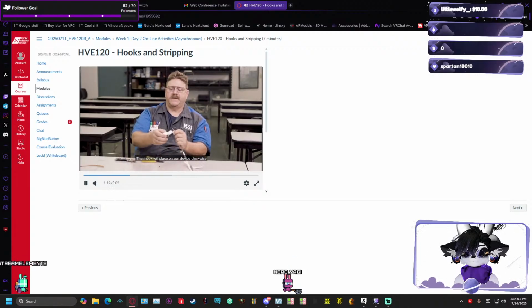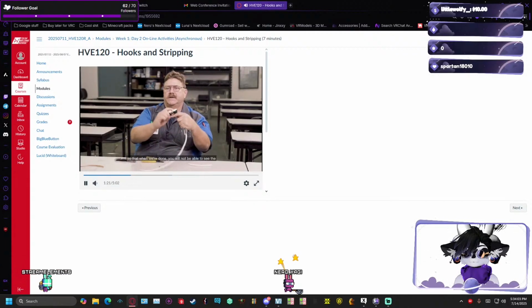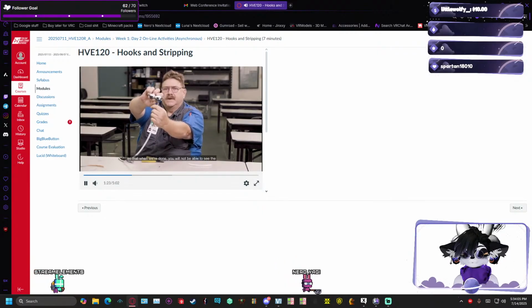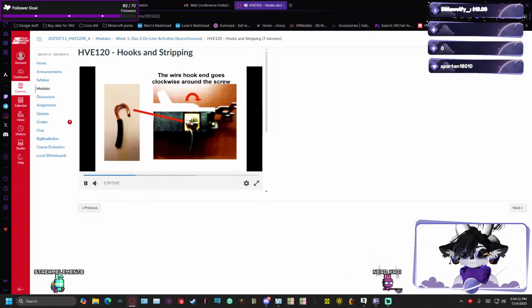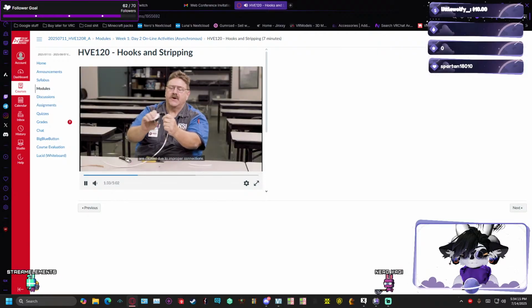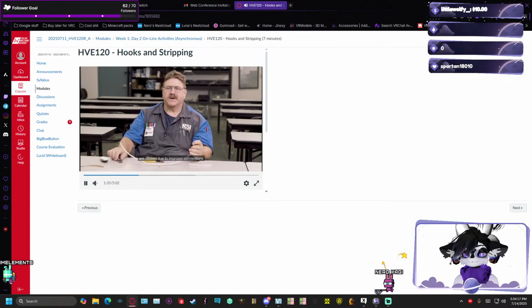And that hook will place on our device clockwise so that when we're done, you will not be able to see the copper outside of the head of the screw. And that's a proper connection right there. It's very crucial. 90% of the electrical failures are caused due to improper connections.